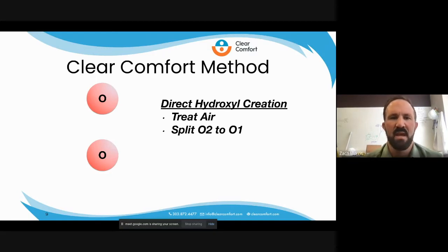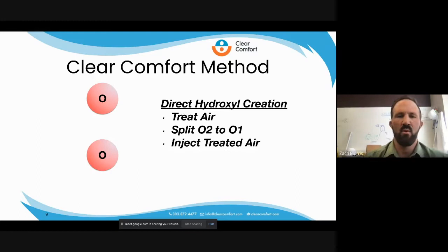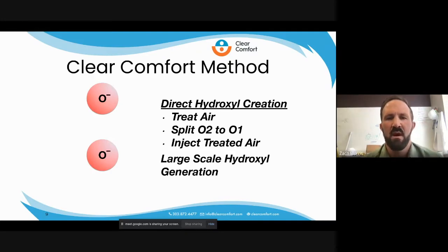We treat the air, splitting that O2 into two O1 molecules. As soon as it comes in contact with the water, those oxygen molecules will grab a hydrogen to create the hydroxyl radicals. The reaction with hydroxyl radicals is virtually instantaneous — it takes place within a few feet of the plumbing. That's why we inject in the main return lines, and there's no need for destruct tanks or contact tanks like you have with ozone systems.